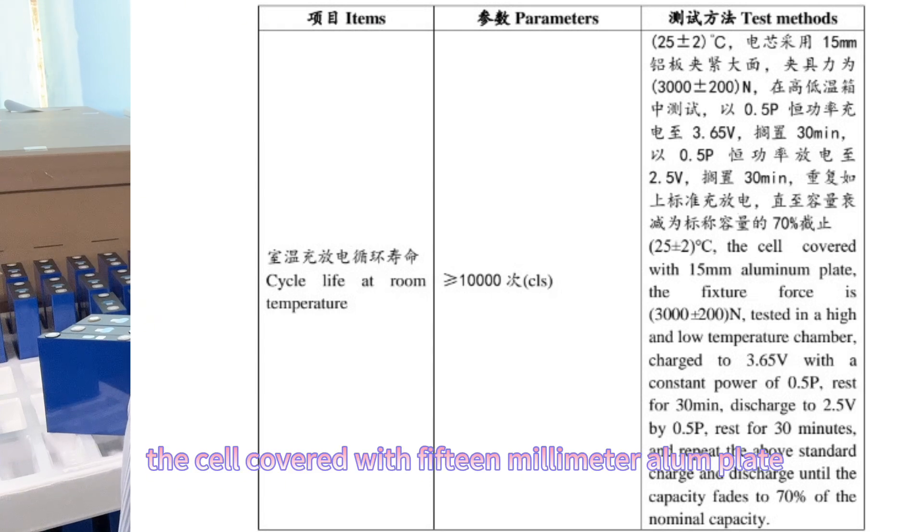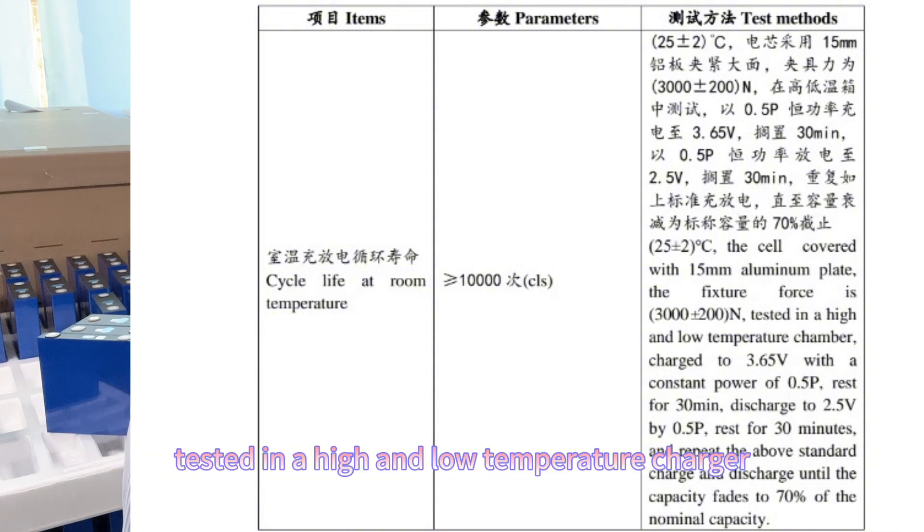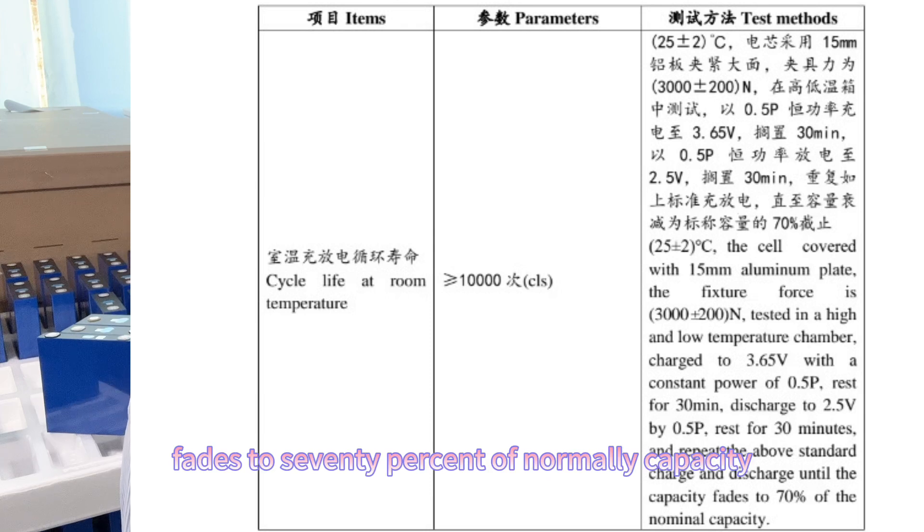Let's read the details. The cell is covered with a 15mm aluminum plate. The fixture force is 3,000 N. Tested in a high and low temperature chamber. Charged to 3.65V with a constant power of 0.5P, rested for 30 minutes. Discharged to 2.5V at 0.5P, rested for 30 minutes. Repeat the above standard charge and discharge cycle until the capacity fades to 70% of normal capacity.